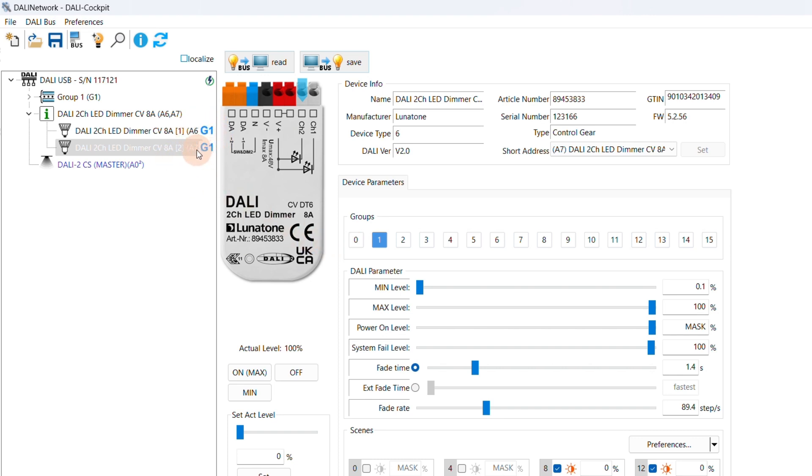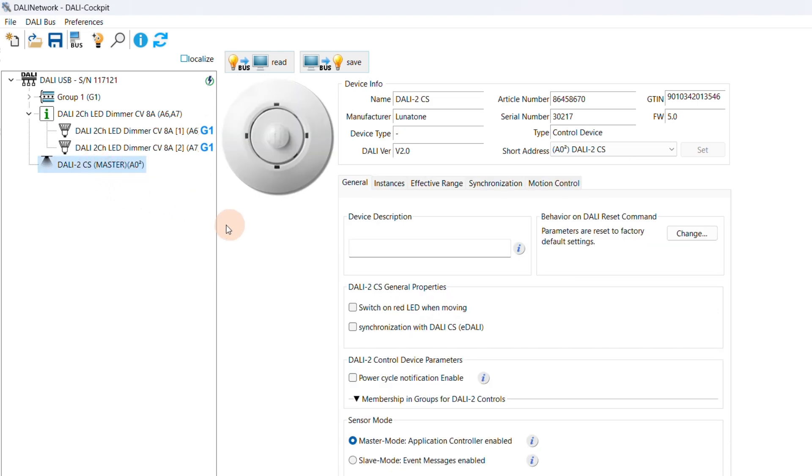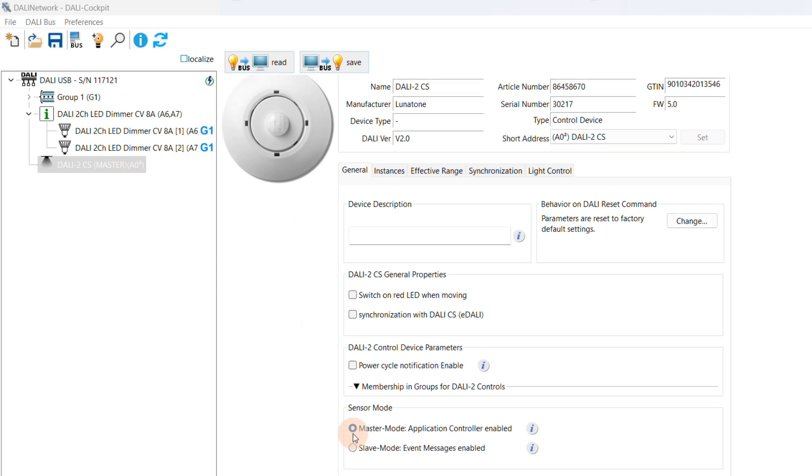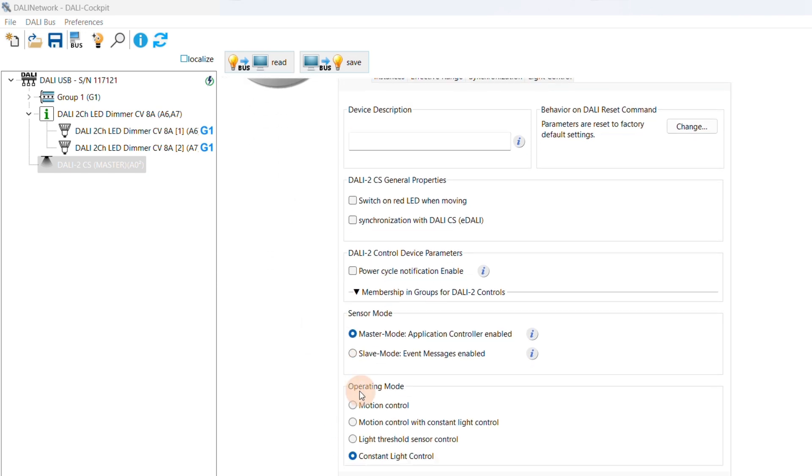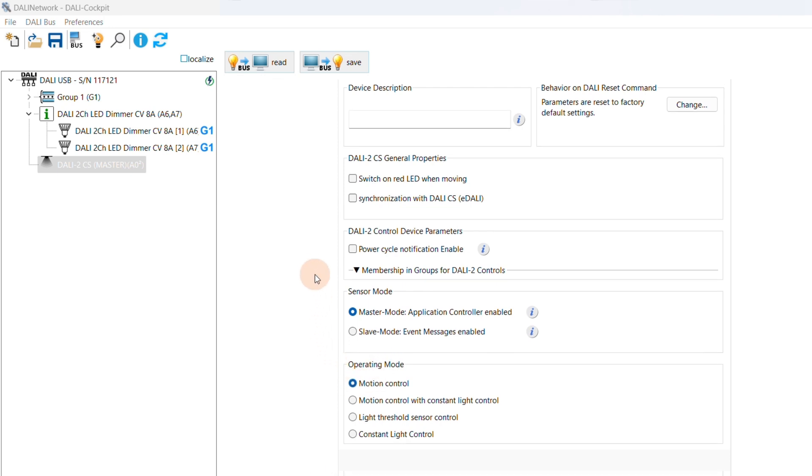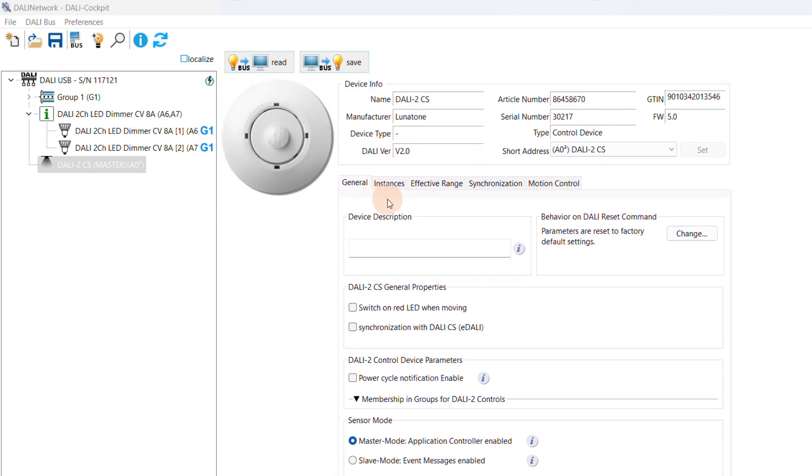Now we go to the settings page of our sensor. First, we check if the master mode is activated. The master mode allows sensors to directly control luminaries. In the operating settings, we select Motion Control, so the lights turn on when motion is detected. We can skip instances since we have activated the master mode.